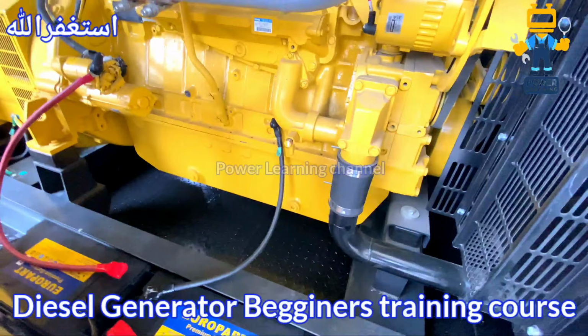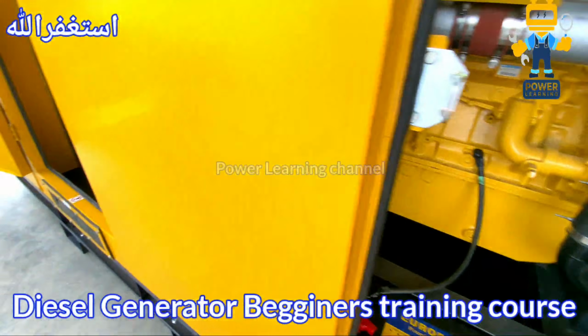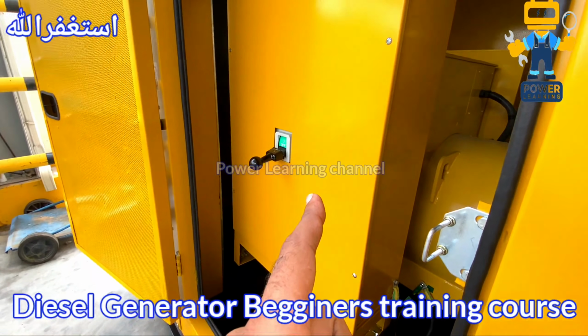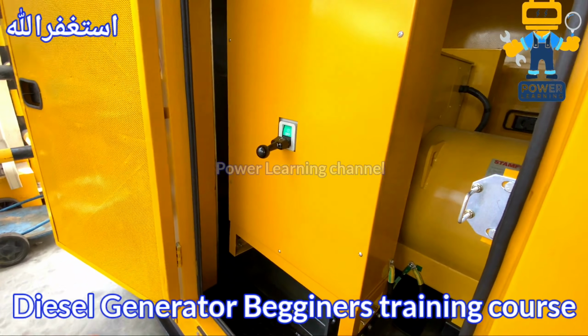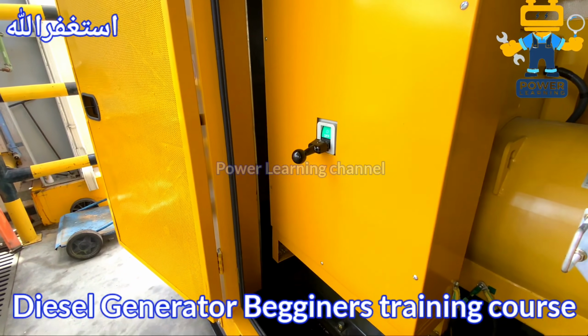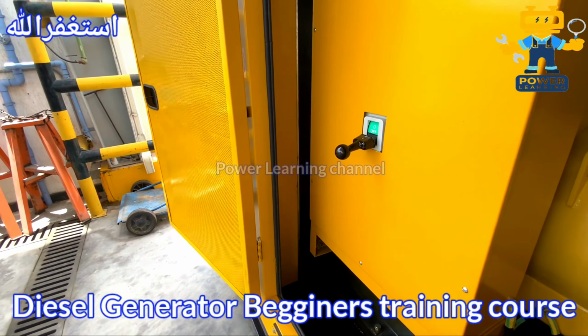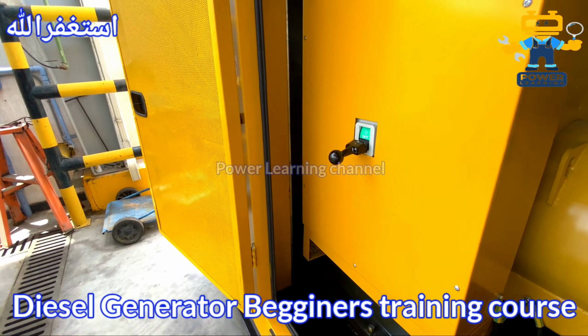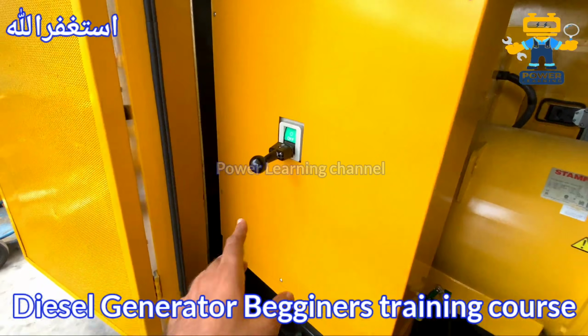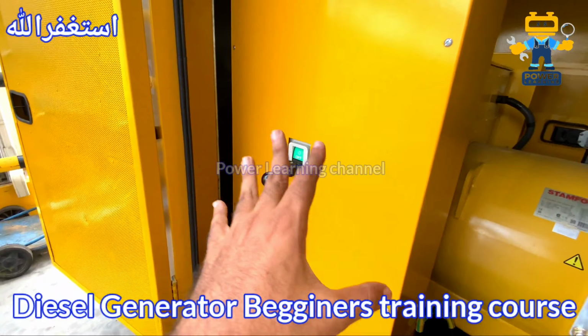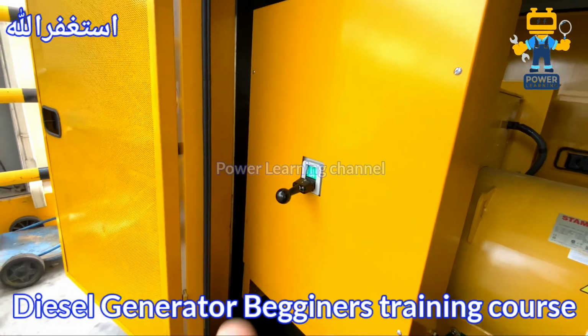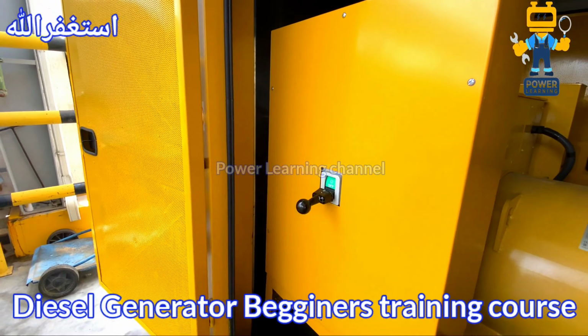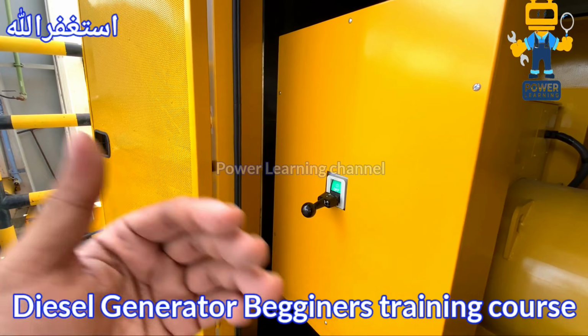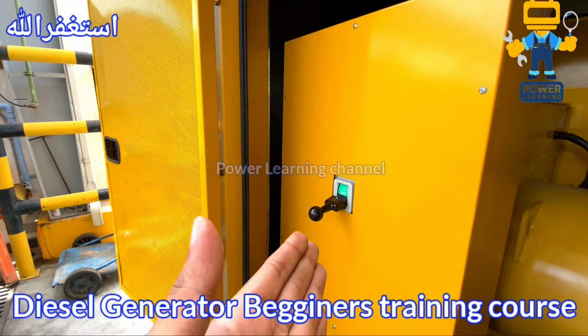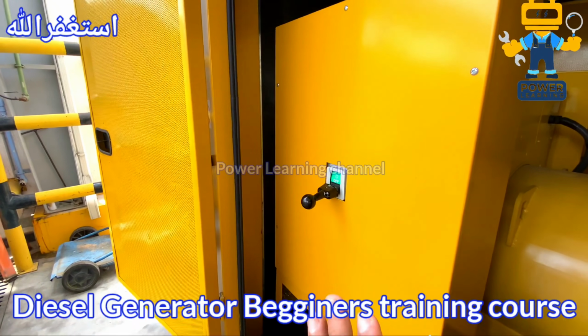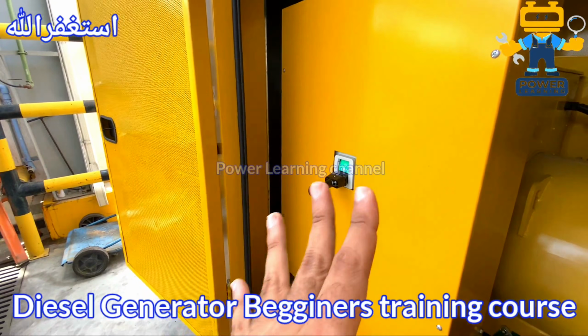Now I will show you another important thing. This is our main breaker, because once we produce the electrical power, we need to send it to our customer side, or to the factory or to the machines to operate. Inside the box we have a breaker as per the rating of the generator. If the generator is small, the breaker size is small. If the generator is big, the breaker size is big. It depends on the total amperage of the alternator, how many kVA and how much current it is producing.